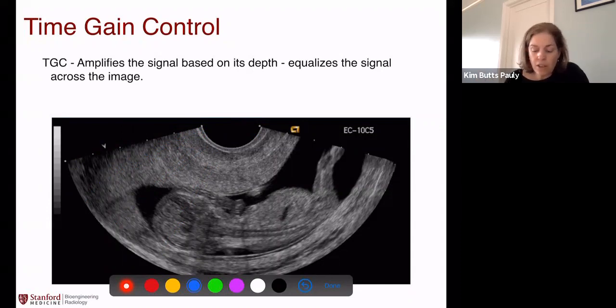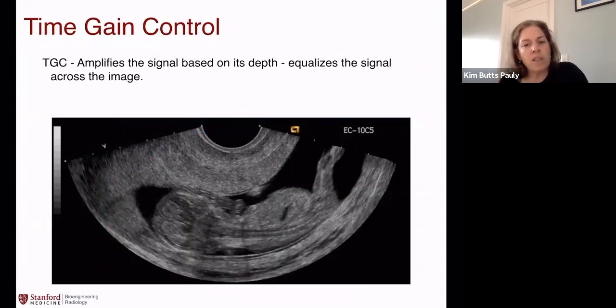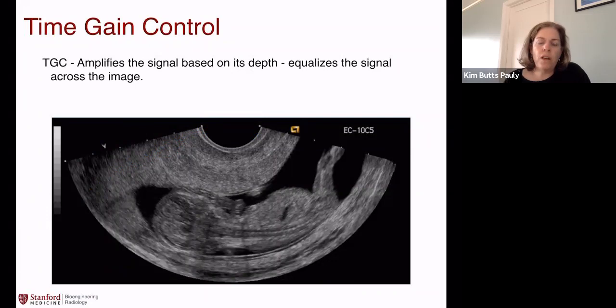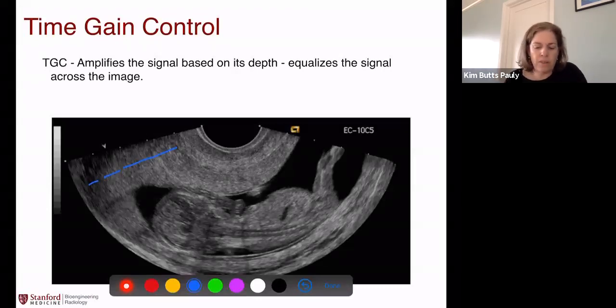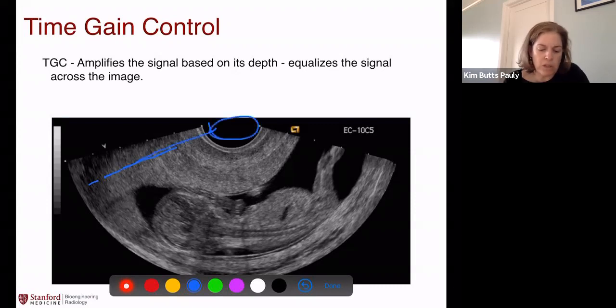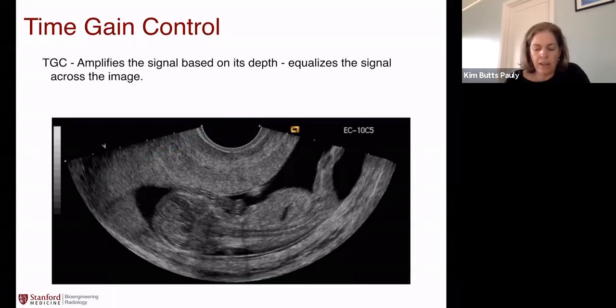The truth is the computer knows it should be attenuated. It knows there's a constant attenuation in soft tissue, and so it's going to compensate for that. All those echoes coming back at deeper depths — it just bumps up the signal and gives it a gain based on the time it's coming back and being measured by the transducer. That's what time gain control is: based on the time, it applies a gain in order to equalize the signal across the image.